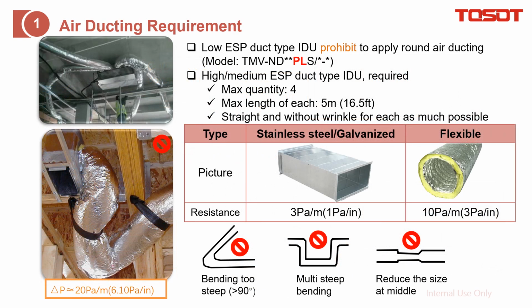Air ductwork requirement. Basically, you can choose these two types, either the rectangular galvanized type or the round flexible type. For the low ESP duct type, basically we do not allow the round one due to too much pressure loss. As for the high or medium ESP duct type, we accept connecting with this one, but the maximum quantity is 4 and the length of each is up to about 16 feet. And also you need to make it as straight as possible, not like this, just like this one.